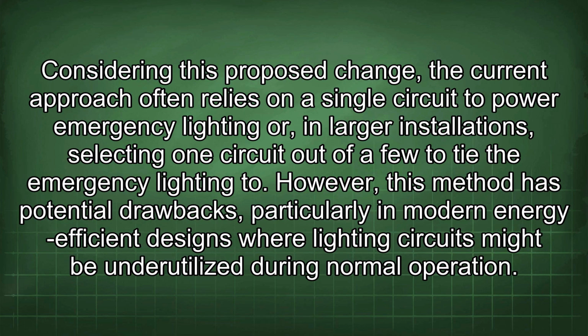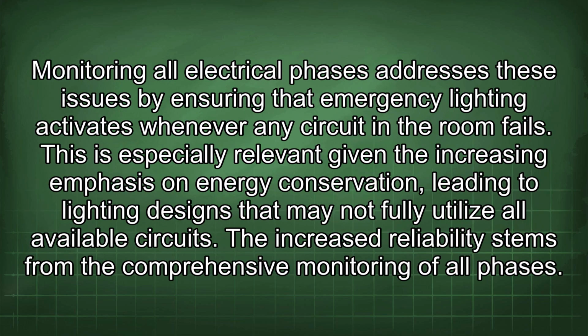Considering this proposed change, the current approach often relies on a single circuit to power emergency lighting or, in larger installations, selecting one circuit out of a few to tie the emergency lighting to. However, this method has potential drawbacks, particularly in modern energy-efficient designs where lighting circuits might be underutilized during normal operation. Monitoring all electrical phases addresses these issues by ensuring that emergency lighting activates whenever any circuit in the room fails. This is especially relevant given the increasing emphasis on energy conservation, leading to lighting designs that may not fully utilize all available circuits. The increased reliability stems from the comprehensive monitoring of all phases.